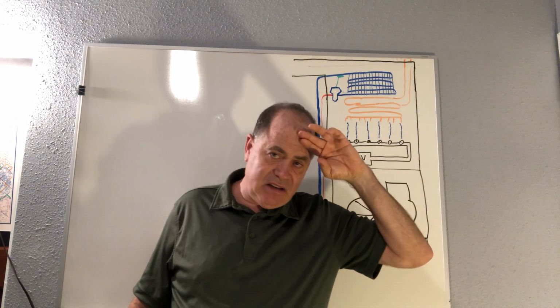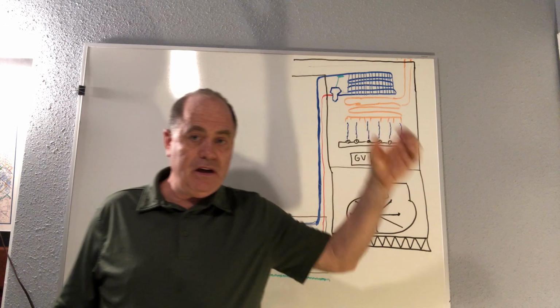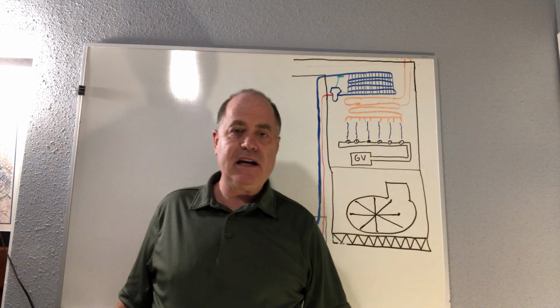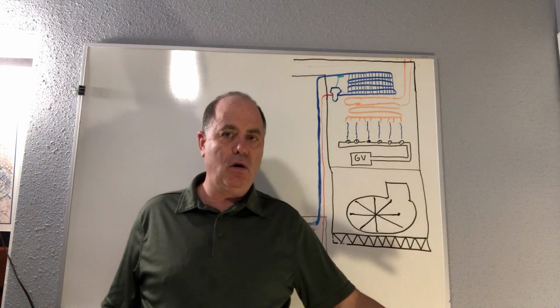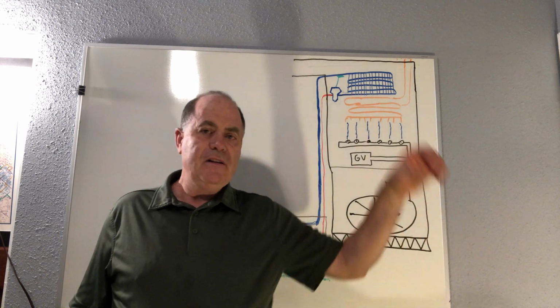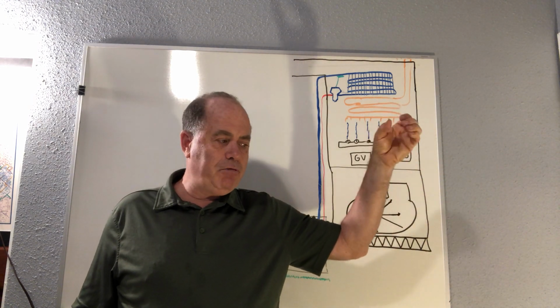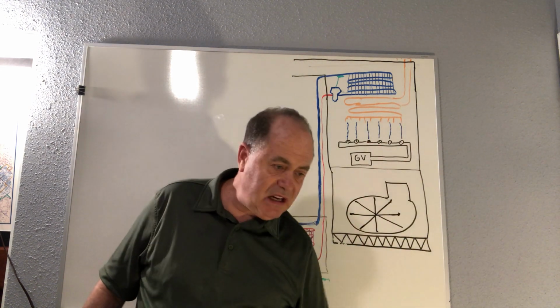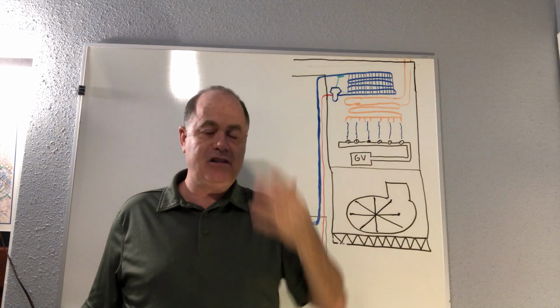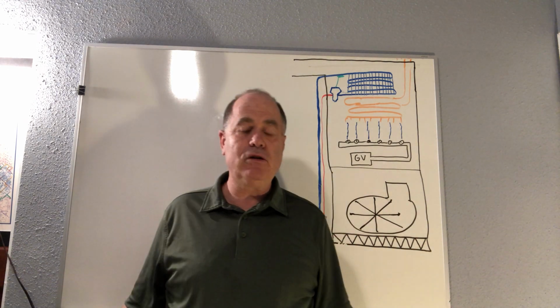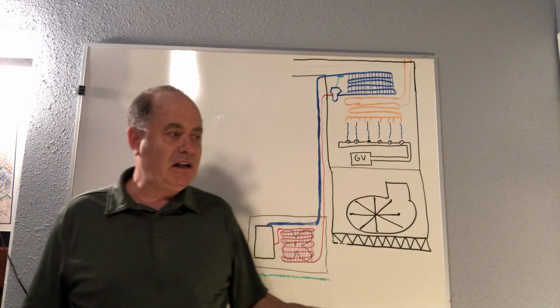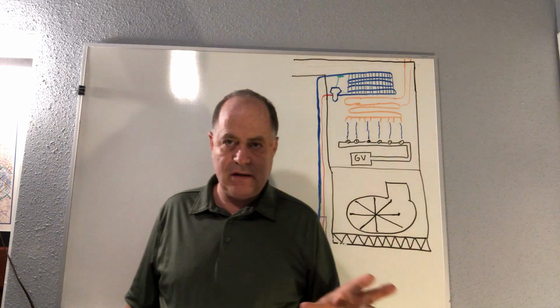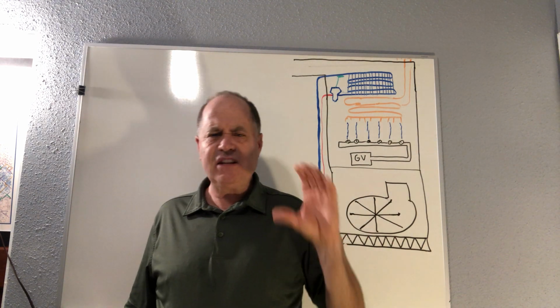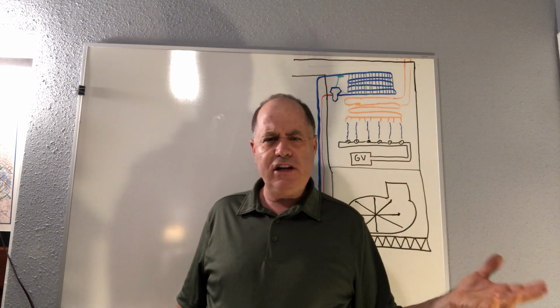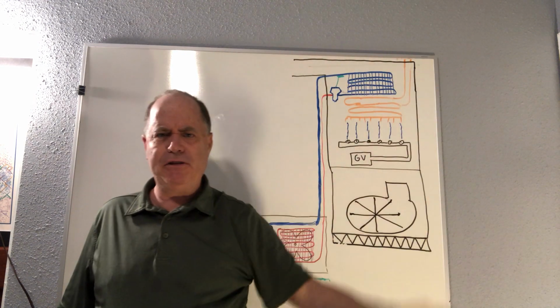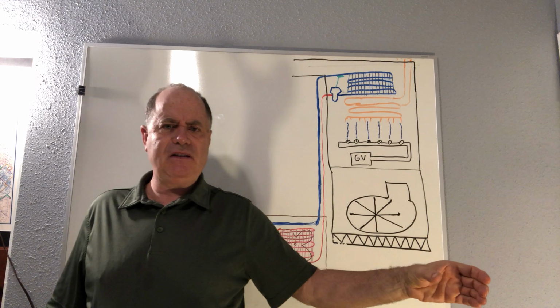And then it does say in another part of the code here that it can't be right against the floor. You have to be up off the floor. I think it's 18 inches. That's so that if it overpressurizes and hits the hot water and steam, it won't hit so hard that it flashes up into your face. It may burn your ankles, but it's not going to flash up and blind you or something like that. Okay, that's why you'll see on hot water heaters and boilers, hey, there's this pipe that's open that just stubs off and stops right here.